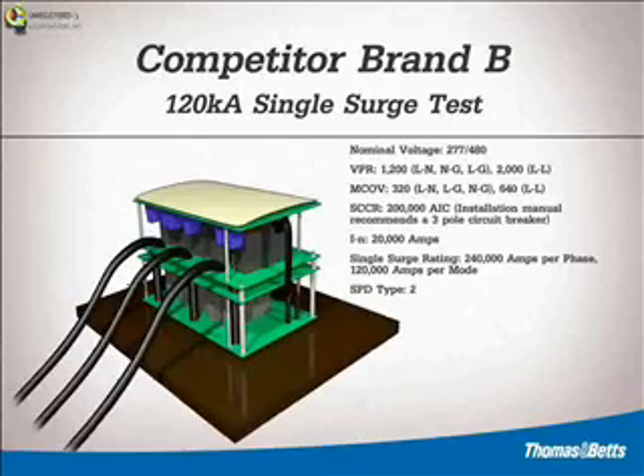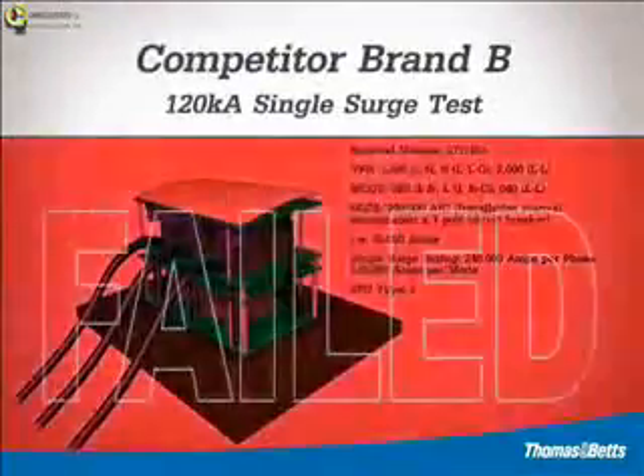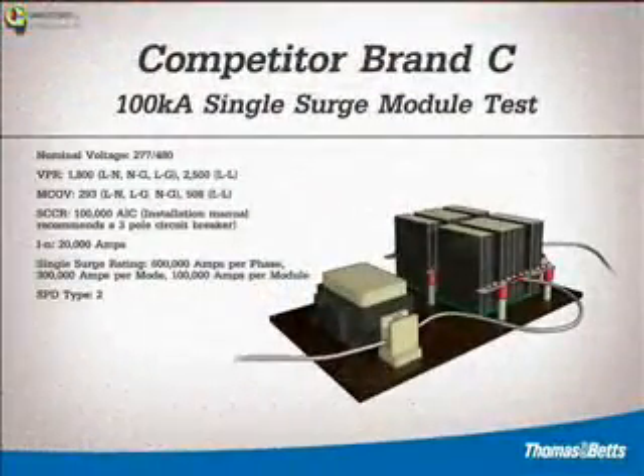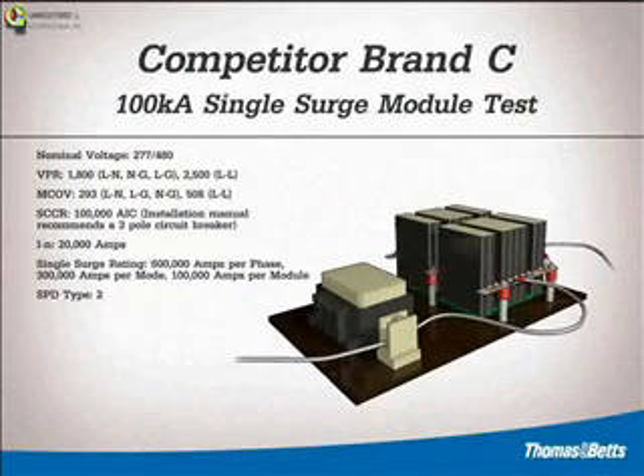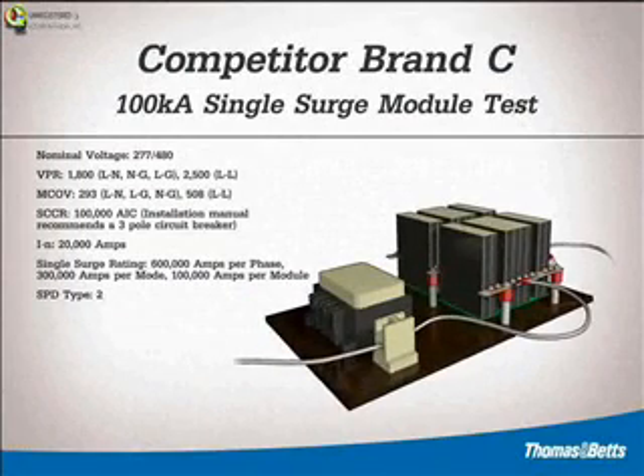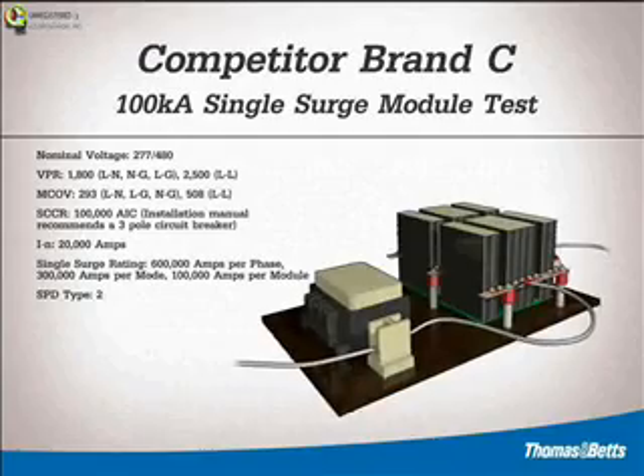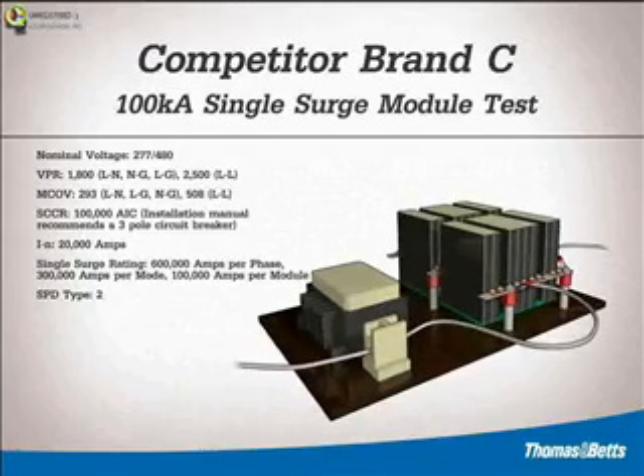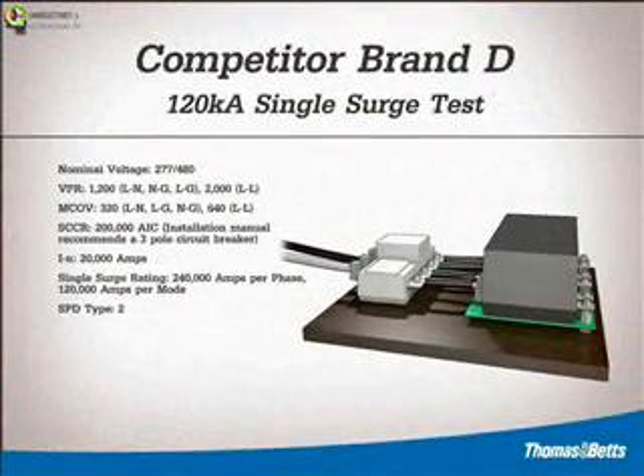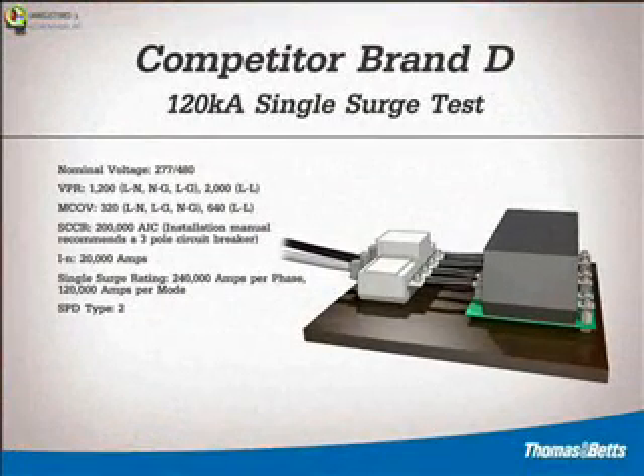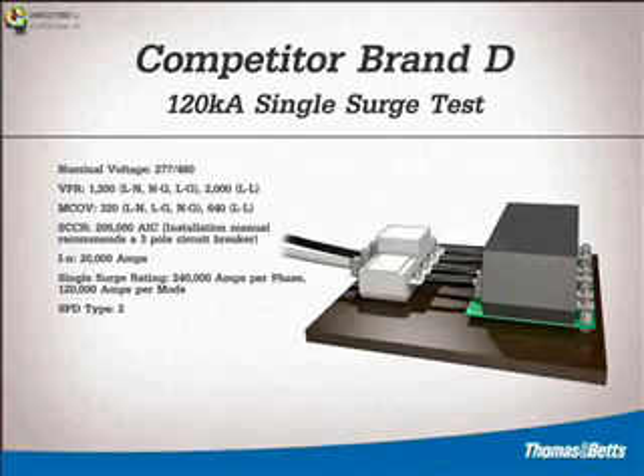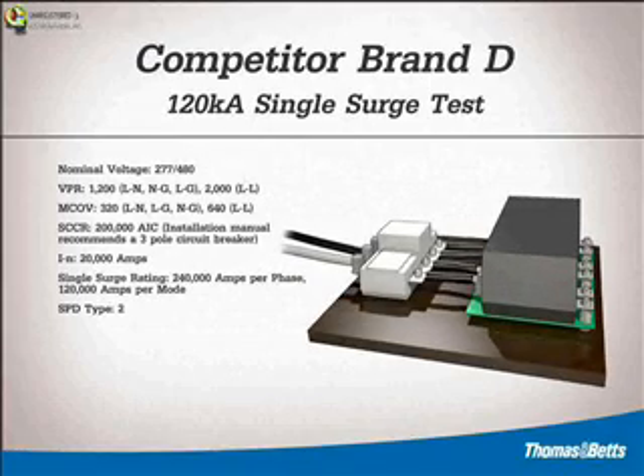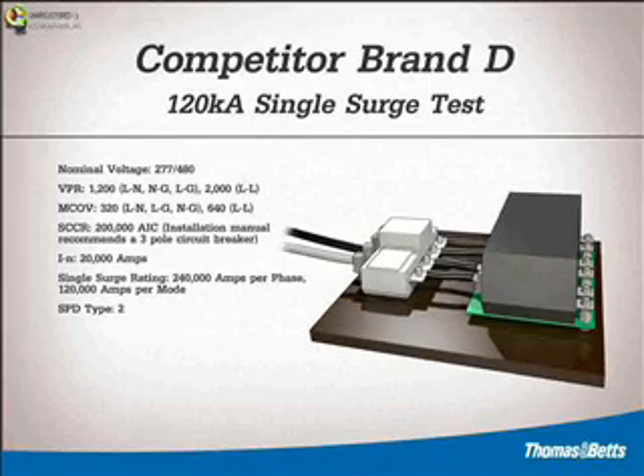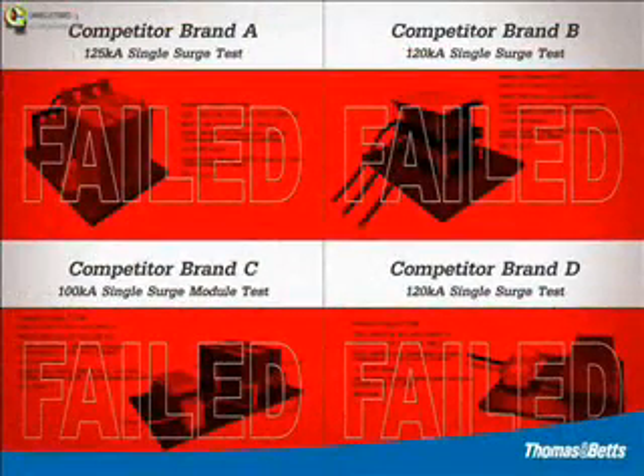Since lightning strikes can include up to 40 individual strokes, these failures would leave downstream equipment vulnerable and unprotected. As demonstrated by the failure of all 4 competitive samples, the surge rating marketed by these manufacturers is a calculated value. Single surge ratings are how surge devices are specified and reflect not only the single surge protection capacity of the device, but the longevity as well. For optimum performance and prolonged useful life, ensure your SPD's rating has been validated by an accredited third-party lab.